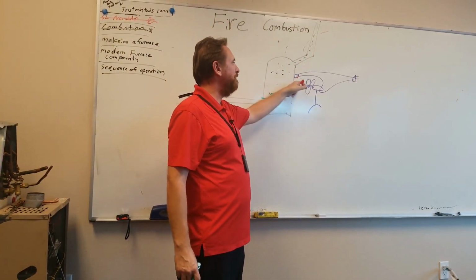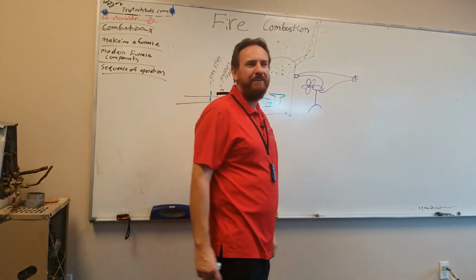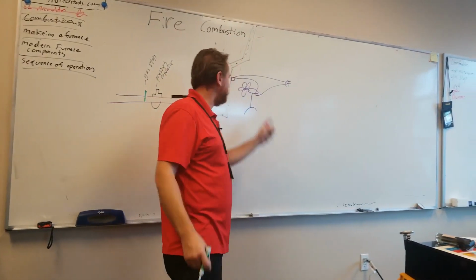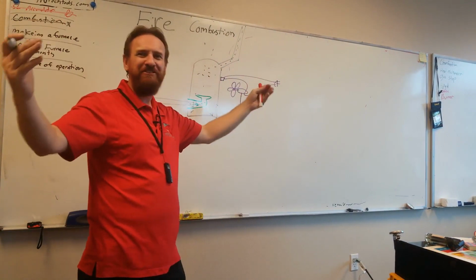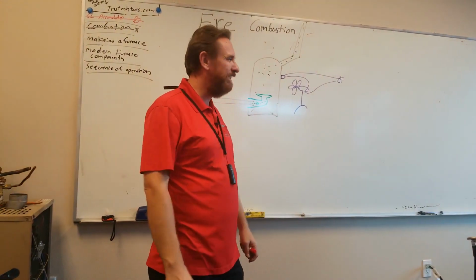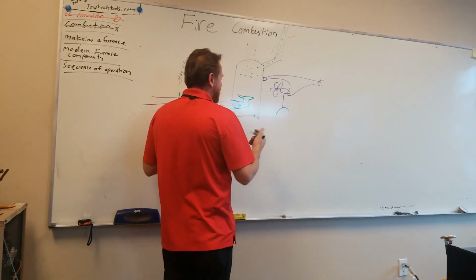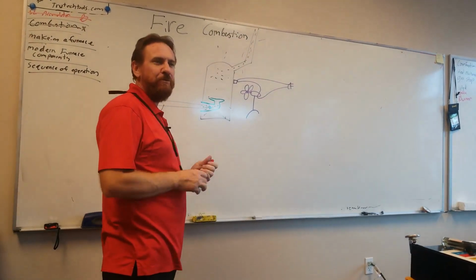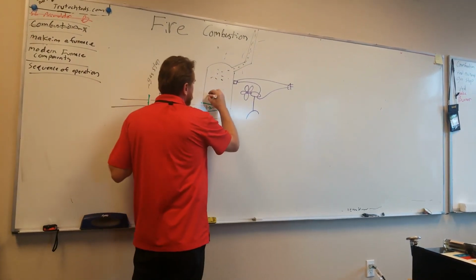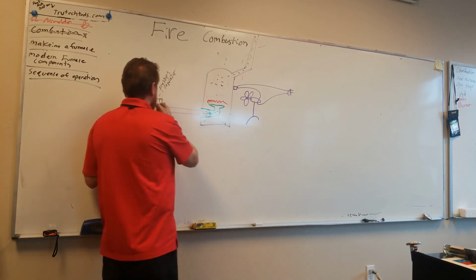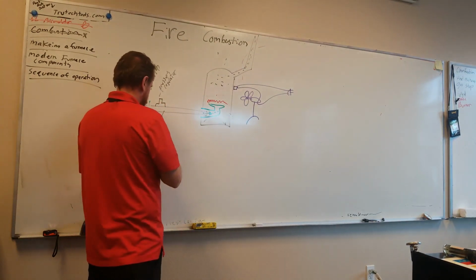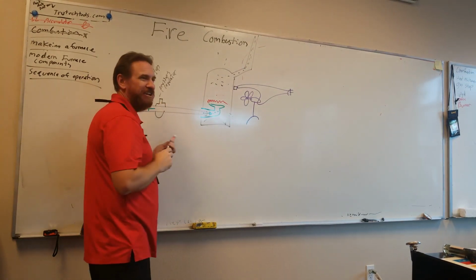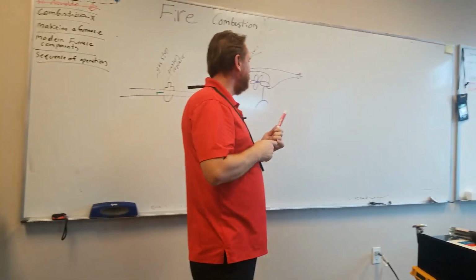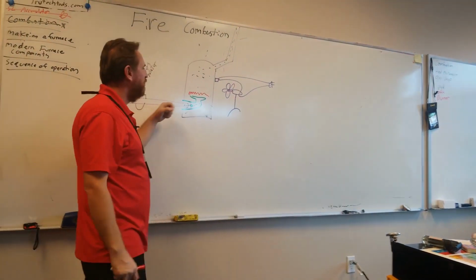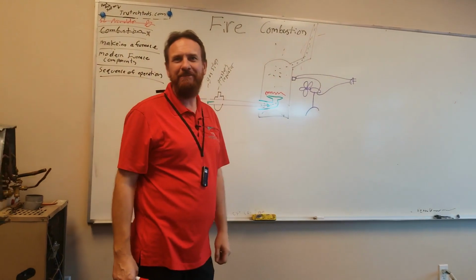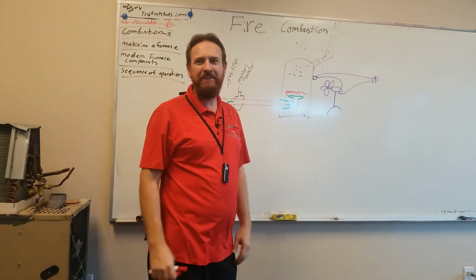This switch is going to keep the fan on to cool the metal off. Eventually that metal's going to cool off. What's going to happen to this fan? Shuts off. That's a perfect thing, right? Isn't it great? So that's what's happening. And then it feels kind of cool. So in the middle of the night, you wake up, you come over there, you open the door, you reach in, you light it with the lighter when you turn this valve on. Sound good, right? The problem is having to open this door, reach in there, and light that flame. Kind of not a fun thing.